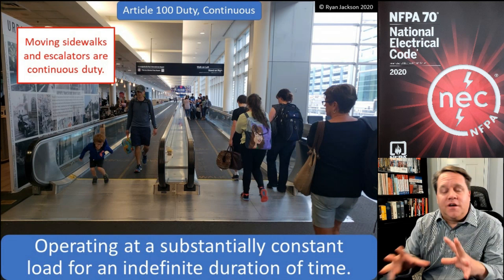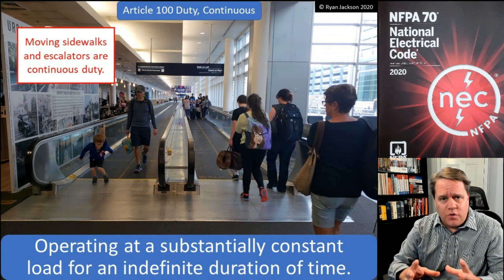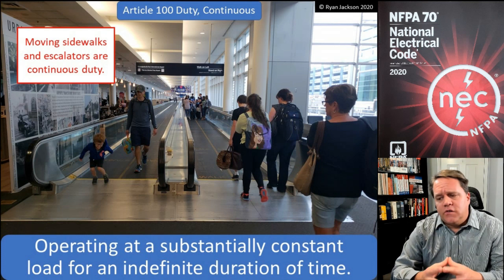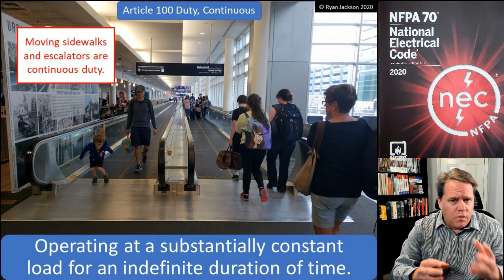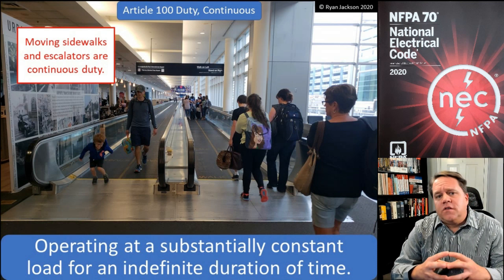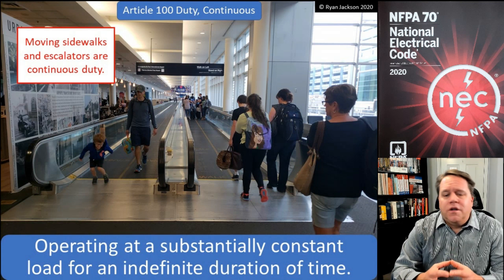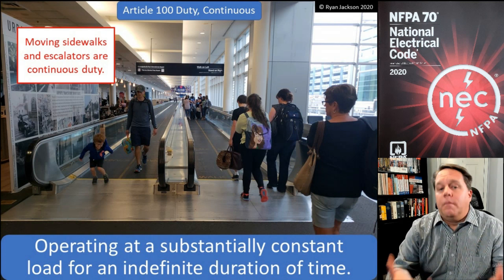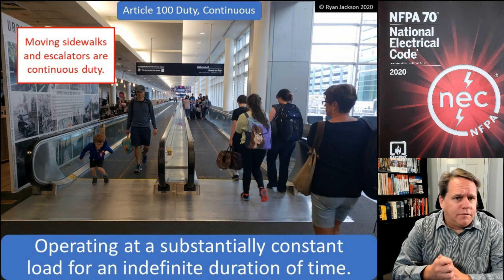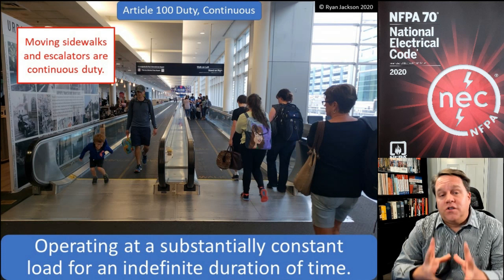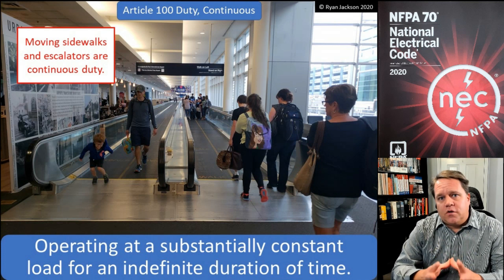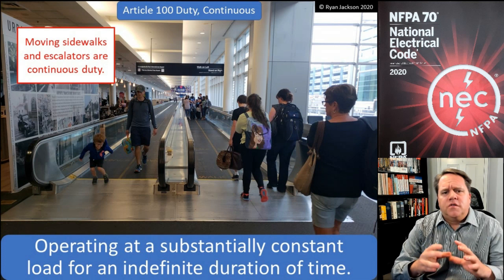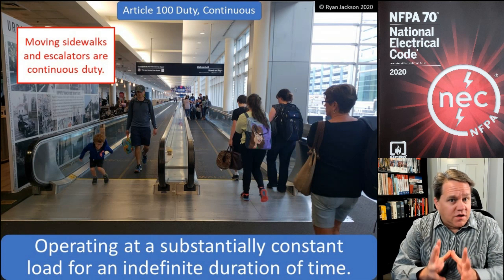We've had some easy ones — now it's time for a couple of tough ones. This is duty and its associated terms: continuous duty, intermittent duty, and things of that nature. These definitions all relate to motors. When you read the term continuous duty, it says it's something that operates at a substantially constant load for an indefinite duration of time. If you go to section 430.22(e), which covers conductor sizing, you'll see that you size conductors for motors based on the type of duty cycle they have.